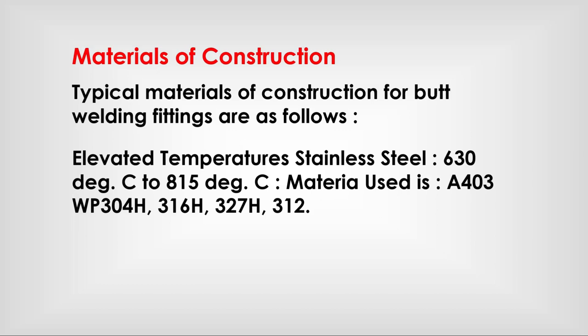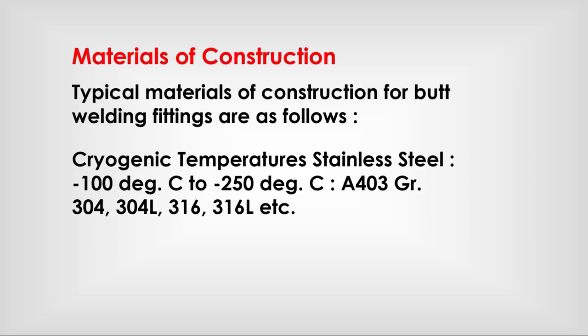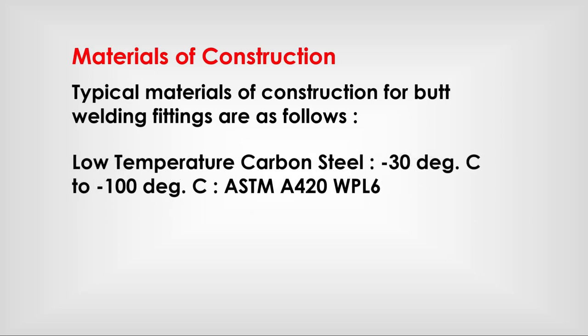Elevated temperature stainless steel (630°C to 815°C): A403 WP304H, 316H, 321H, 347H. Duplex stainless steel: A815 UNS S31803. Cryogenic temperature — stainless steel (−100°C to −250°C): A403 Grades 304, 304L, 316, 316L, etc. Low temperature carbon steel (−30°C to −100°C): ASTM A420 WPL6.